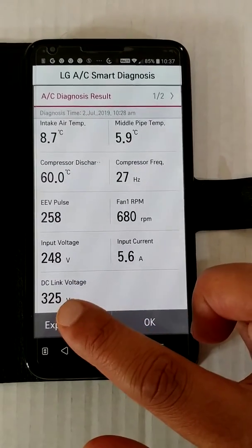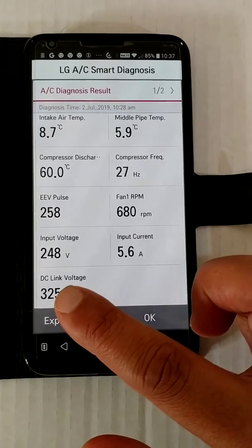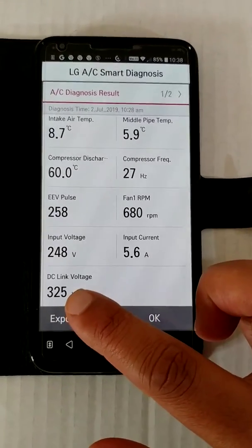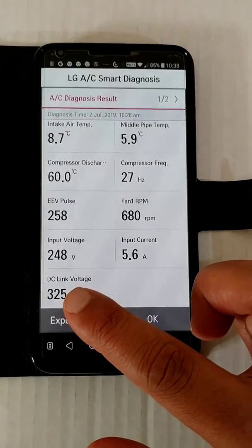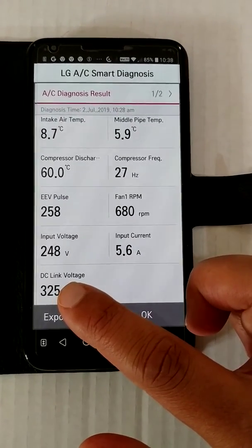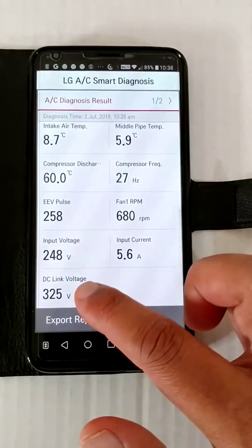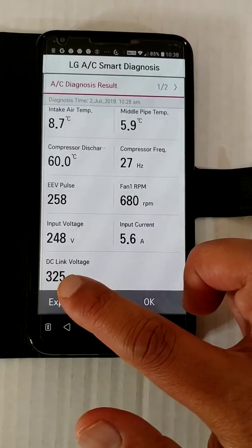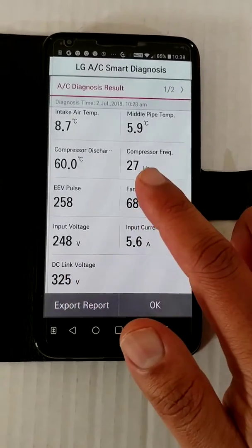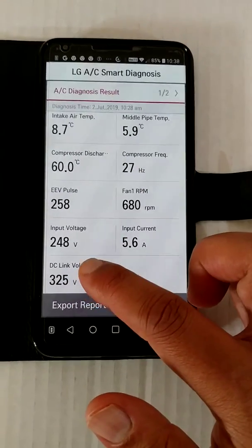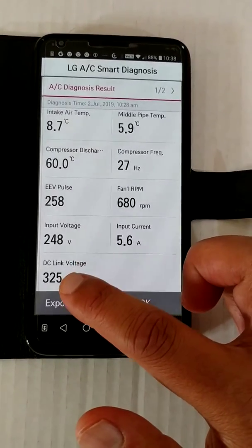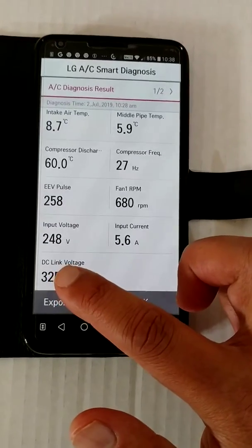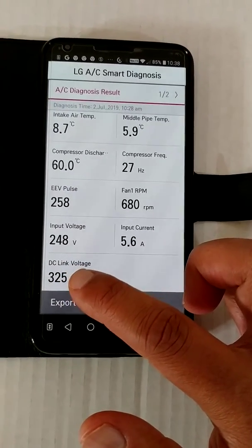The DC link voltage is the voltage after it's been rectified — currently at 325 volts. This voltage can be boosted by the reactor, the power factor corrector circuit, up to 400 volts. If this split system were running at a higher speed, the voltage would go up and drive the compressor faster. Some models call this technology PAM — pulse amplitude modulation — where the bus voltage is boosted or lowered.